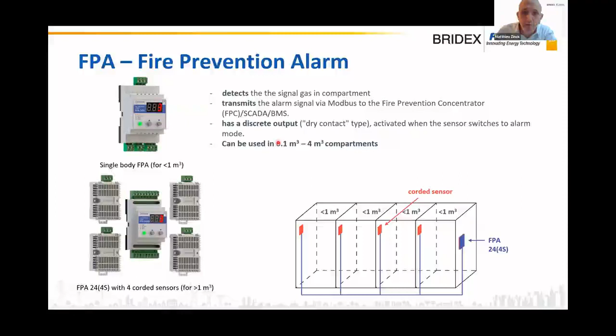As I mentioned before, the FPAs are equipped with a discrete contact output and Modbus communication that allows you to connect it with the SCADA or the BMS. So here is another important part, looking at security. The FPA is constantly checking the ambient air inside the compartment. Basically, the sensitivity of the electronic device is very low. It's about 10 ppm, and the threshold usually for a cubic meter is set at 150 ppm.